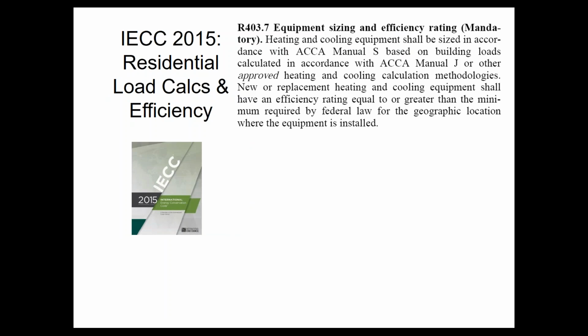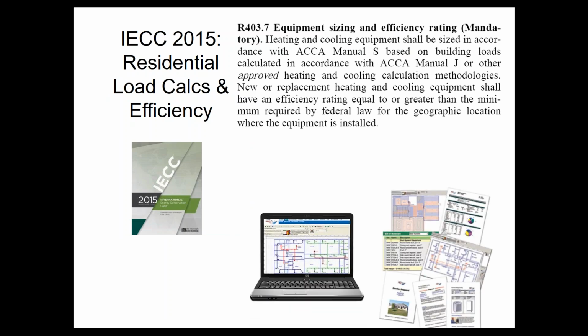All right, residentially also, you have to have load calculations for the systems that you're installing. The load calculations have to be ACCA Manual J or other approved calculation method. Other approved means your local jurisdiction says, oh, you don't have to do ACCA J, you can do this ASHRAE method instead, or whatever else they would approve. For most of us, it means ACCA Manual J. In addition to ACCA Manual J, you have to do ACCA Manual S. J is the load calc, Manual S is the system sizing and selection. So once I have the load calc and it says how many heating and cooling BTUs I need, I then have to use Manual S to make sure I size equipment in accordance with those load calcs.